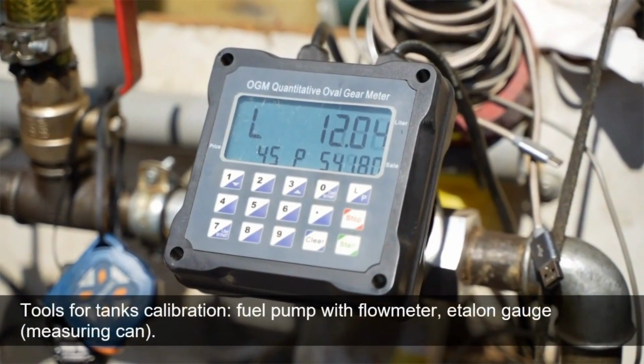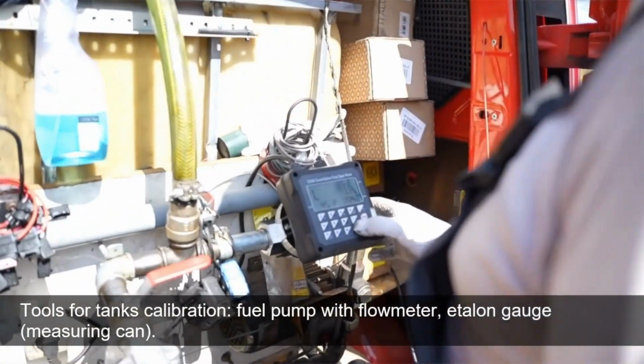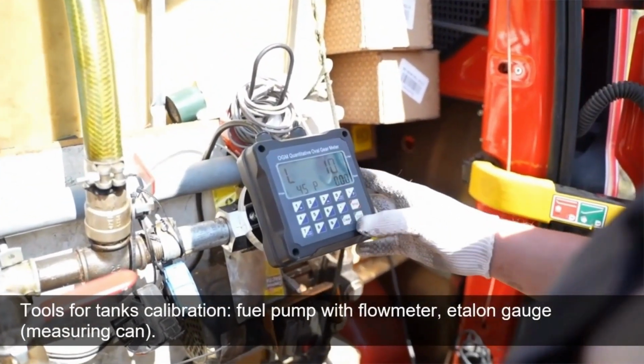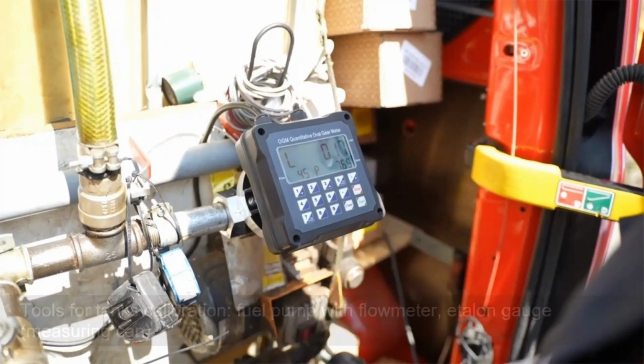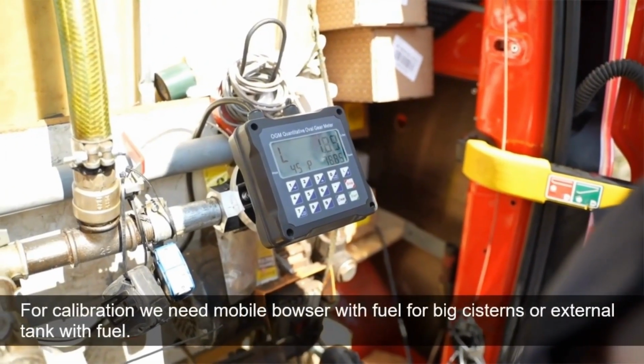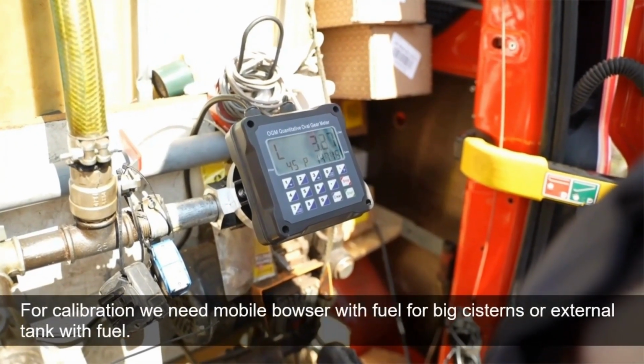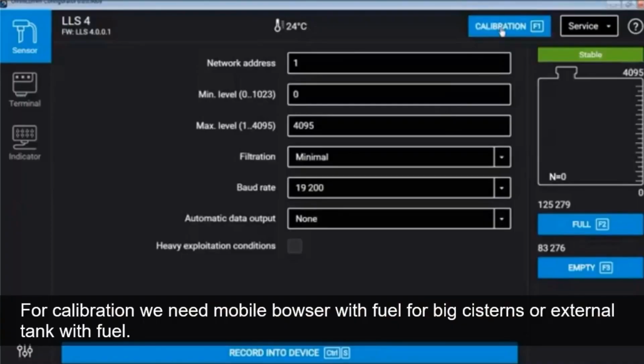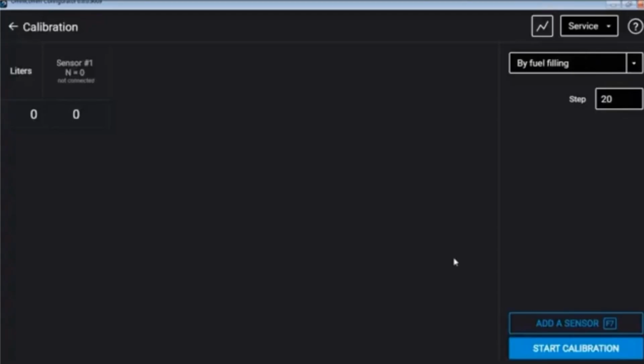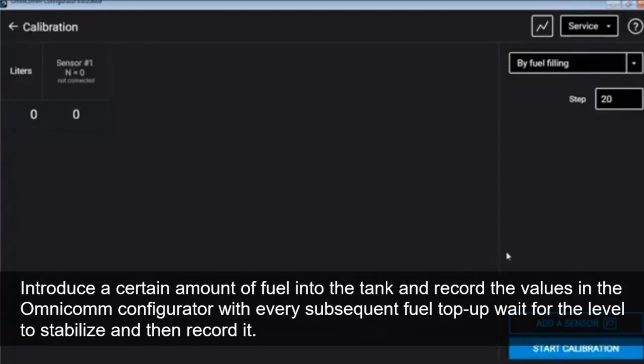Tools for tank calibration: fuel pump with flow meter, etalon gauge, measuring can. For calibration, we need a mobile bowser with fuel for big cisterns or an external tank with fuel. Introduce a certain amount of fuel into the tank and record the values in the Omnicomm configurator with every subsequent fuel top-up. Wait for the level to stabilize and then record it.